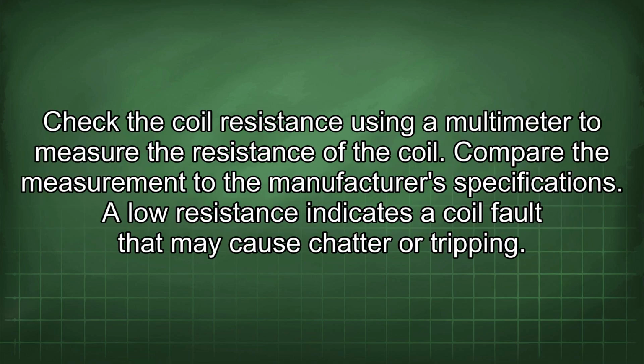Check the coil resistance using a multimeter to measure the resistance of the coil. Compare the measurement to the manufacturer's specifications. A low resistance indicates a coil fault that may cause chatter or tripping.